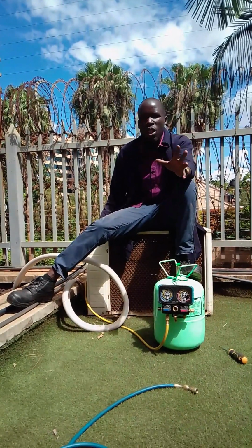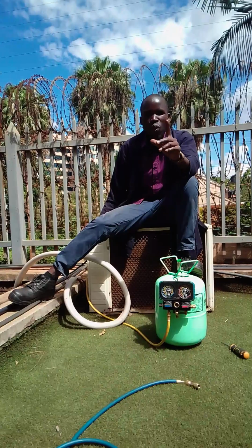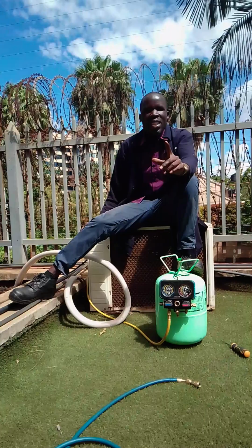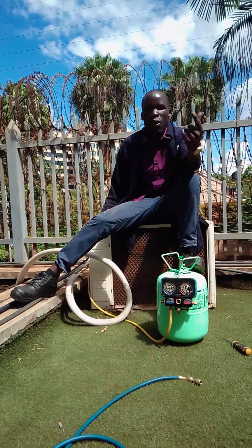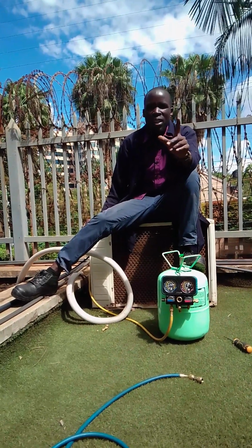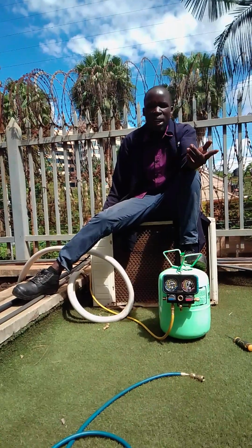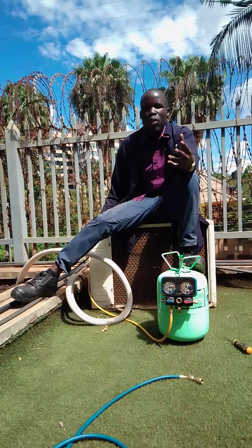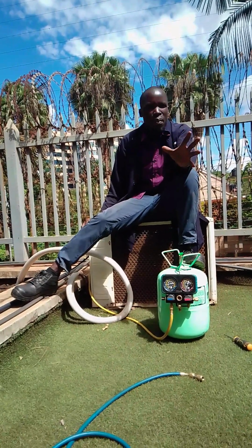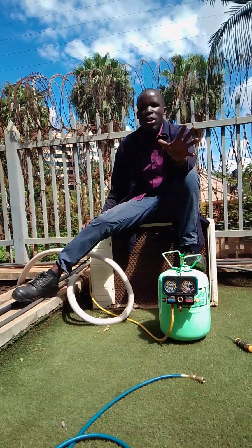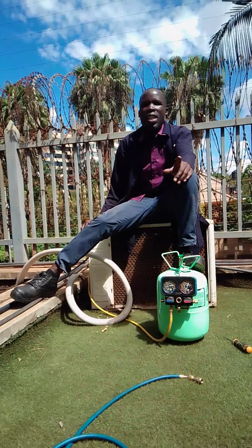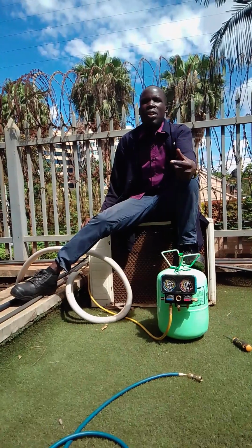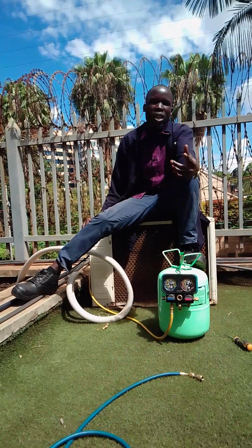You first disconnect all the indoor units and start powering them one by one. When you power the one having the error, the outdoor unit will still be displaying that H7. If that is the one, then you rectify it. But if, by chance, all the indoor units you power do not bring the error code, it means none of those you have powered have errors. You continue powering until the error comes, and that is how you can analyze.